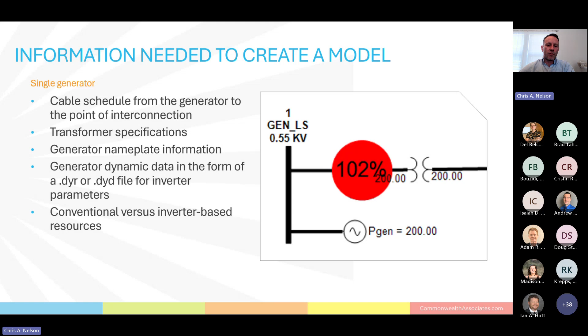You'll definitely need the generator nameplate information, and usually you'll want a D curve too, so you know exactly how much reactive power it can put out. Then you need to either have or create a dynamic file, usually a DYR or DYD file. For a spinning conventional generator, you can usually create that with the generator's parameters, but for the inverter, you really need to get that from the manufacturer—there's not a way to create it.